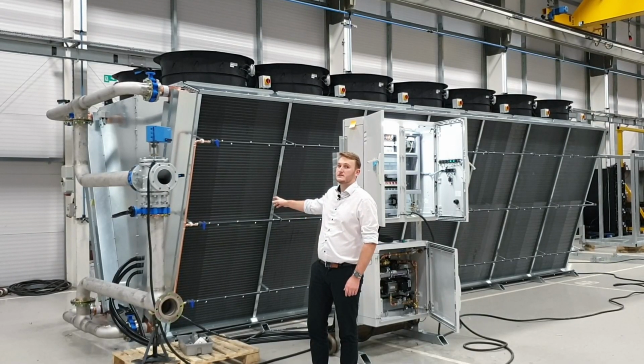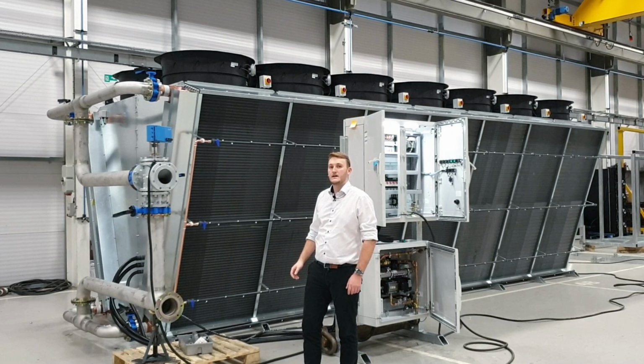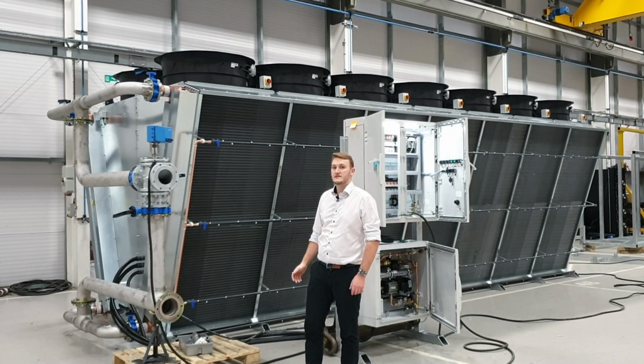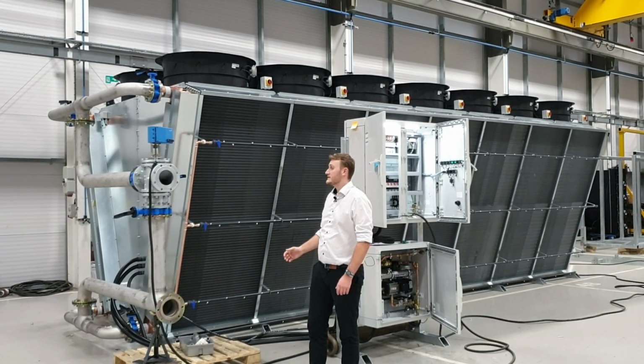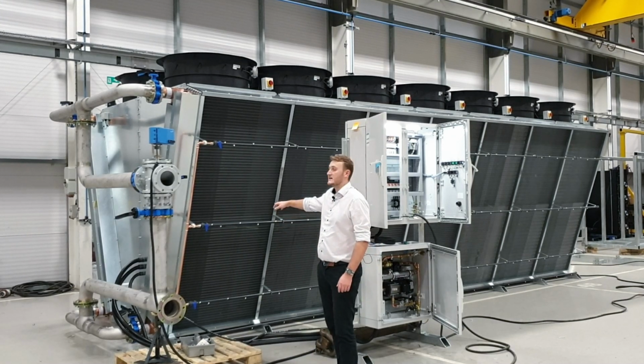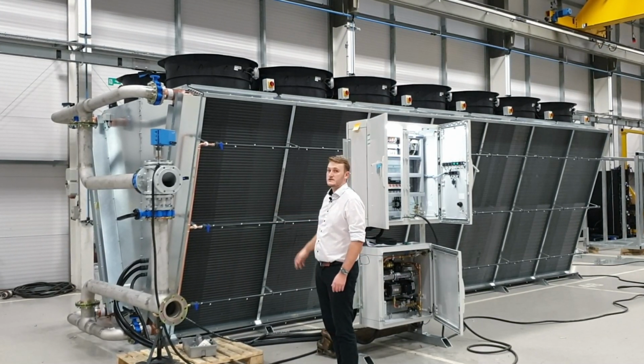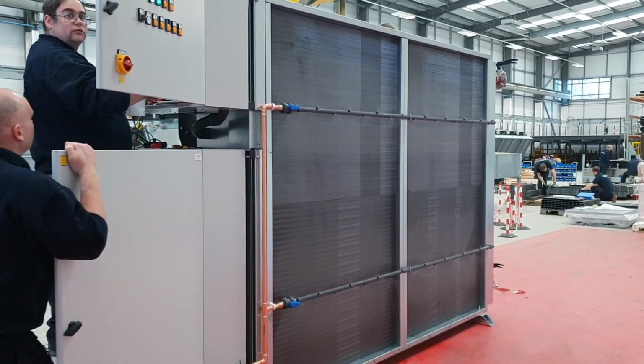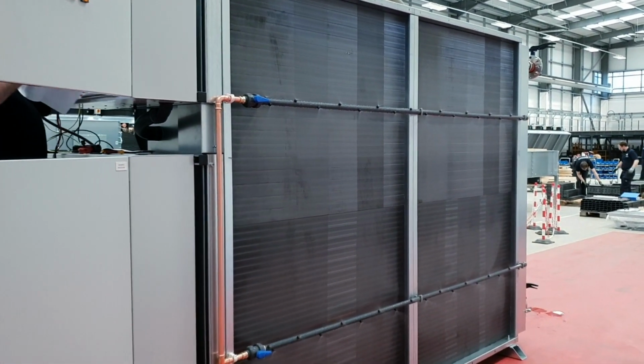As it's an adiabatic cooler, it typically only operates in a wet mode for about 3 to 5% of the year. The remainder of the year it will operate in dry mode. These nozzles here will mist water into the air through the hottest portions of the year, pre-cooling it, meaning that we can hit the temperatures required year-round.